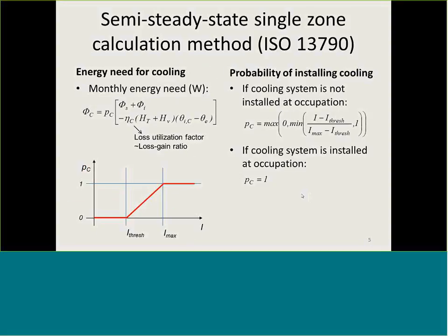Okay, is cooling then dealt with? Also, cooling is defined based on the ISO standard, in which the monthly cooling energy need is calculated by considering the heat gains and subtracting the useful heat losses, in which in this case a loss utilization factor is introduced.